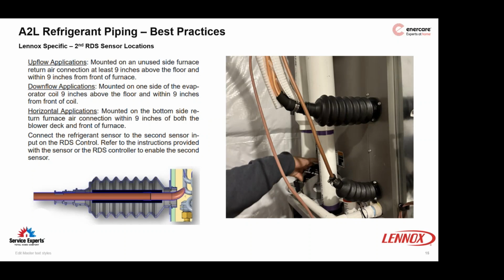So if your room doesn't qualify for size, if you have additional joints in the line set, there's a couple of different qualifying factors within the manual that say if you have this extra joint, or you don't have enough TA minimum, or you have a spark generating device in the room, you can add a second sensor. This is Lennox's approach. All of the other manufacturers outside of Lennox and ADP are not using a second sensor. They're relying on a single sensor within the coil to pick up any refrigerant detected to start those mitigation processes.